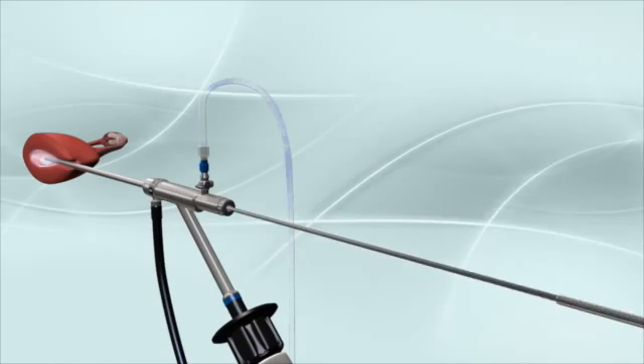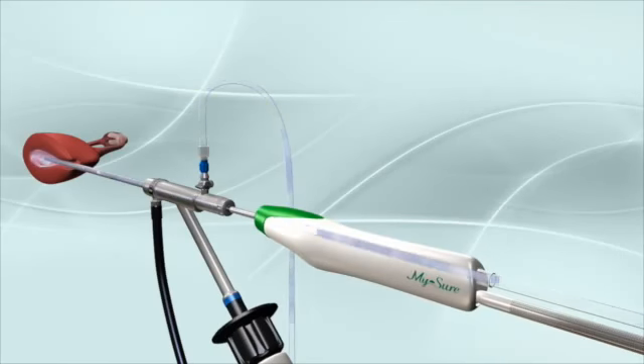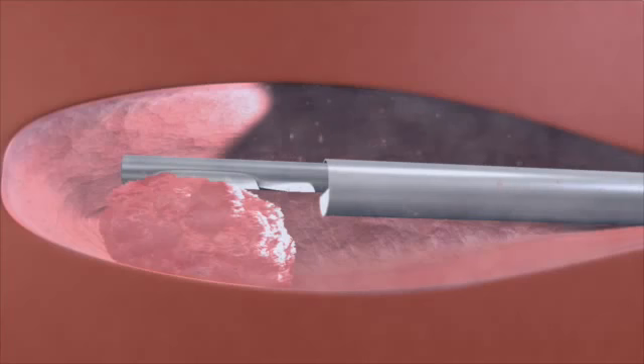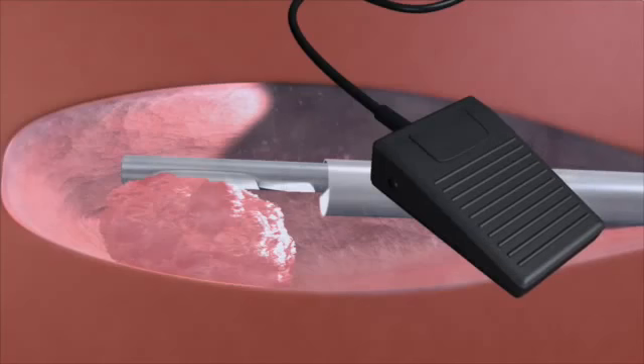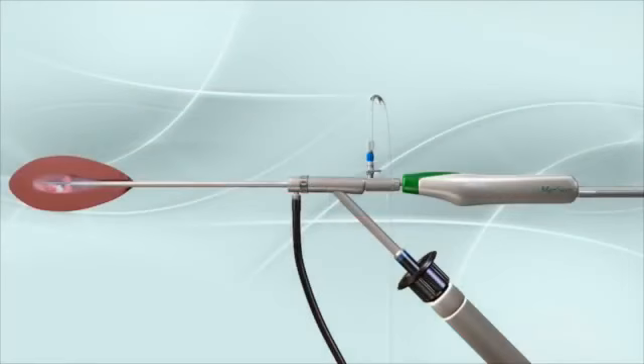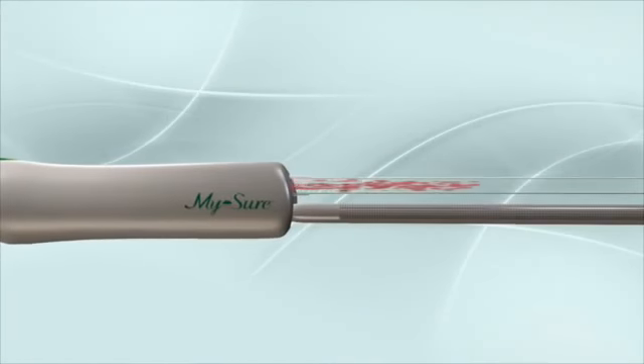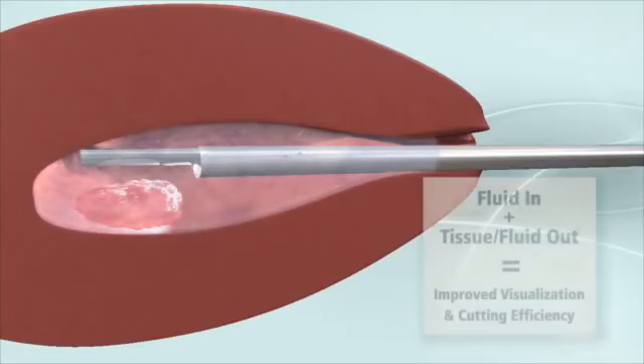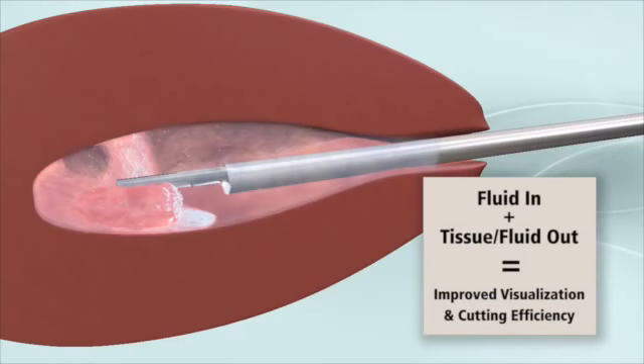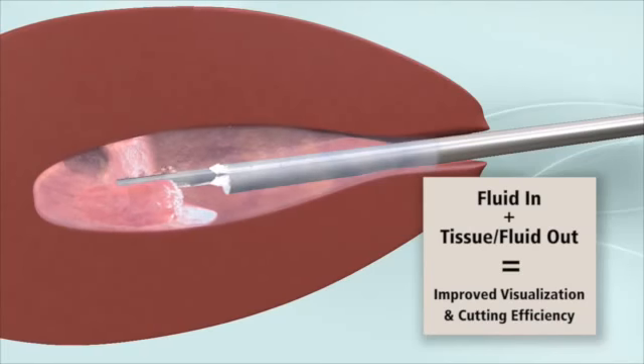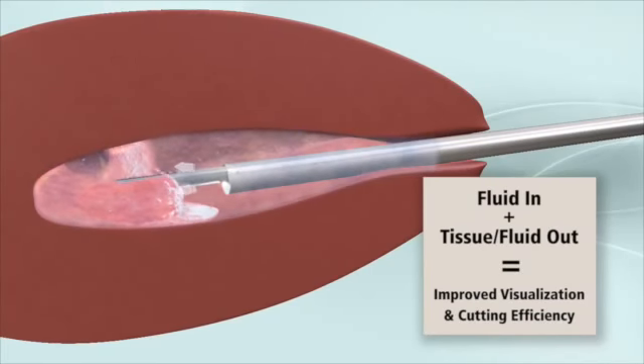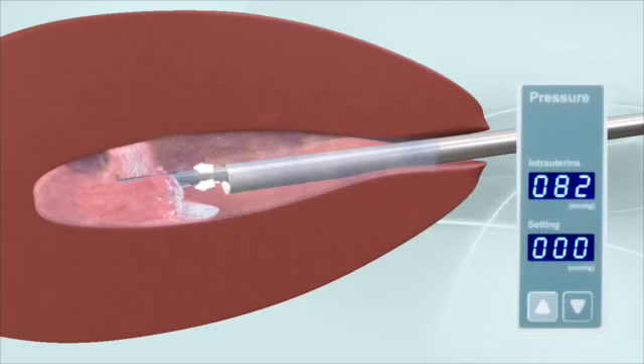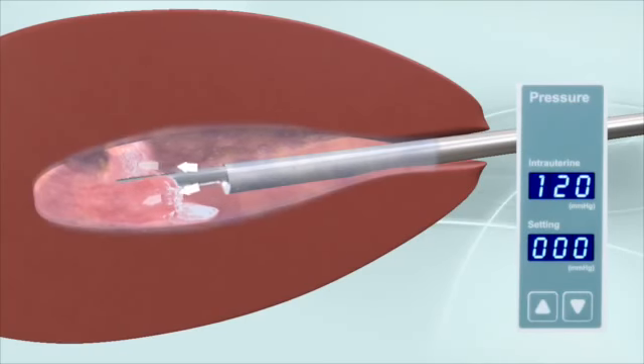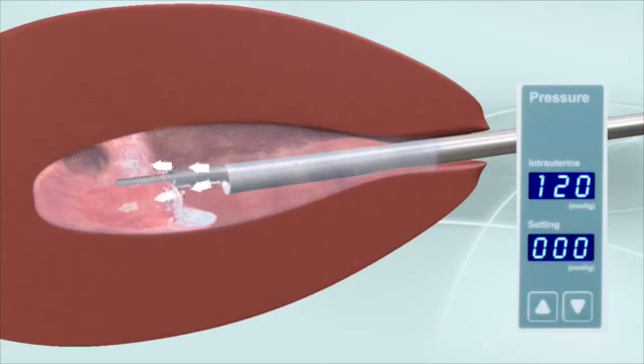The Myosure device now becomes the outflow channel. Active suction is required to remove tissue through the Myosure device. When the Myosure foot pedal is activated, the cutting window is opened and suction pulls fluid and tissue from the uterine cavity through the Myosure device and into the tissue trap. To maintain distension while suction is activated, infusion of fluid into the uterus must be at a fluid flow rate and pressure to establish a balance between the two. This may necessitate periodic adjustments of increased pump pressure to maintain the desired uterine distension.